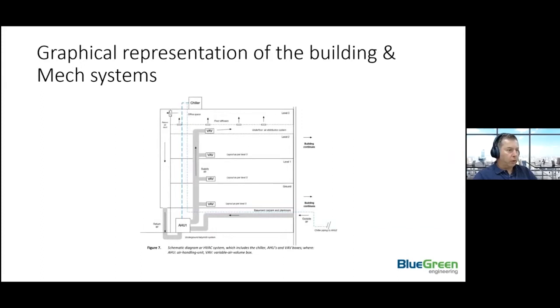Thank you. To better understand what we did as engineering consultants in this building, I've added a simple diagram here which explains the main air conditioning components of the building and the main energy users. One of the main ones on the roof was the chiller. This produces hot or cold water depending on whether it's in cooling or heating mode. This hot or cold water is transferred to the AHU, the air handling unit. The purpose of the air handling unit is to take the energy from the hot or cold water and create hot or cold air, which is used to condition the space. So from the air handling unit, this conditioned air goes to the VAV box, which regulates the volume of air that is supplied.